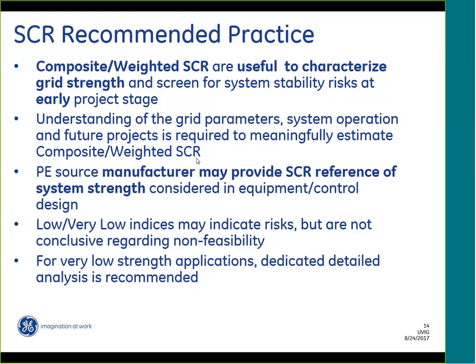Typically, the manufacturer of the power electronic sources, particularly in relation to the inverter controls, may provide the short circuit ratio of reference, meaning the short circuit ratio that was considered in the design of the equipment. If the short circuit ratio in the application is within what was considered in the design, the manufacturer will probably state that the application has a very low risk of instability.